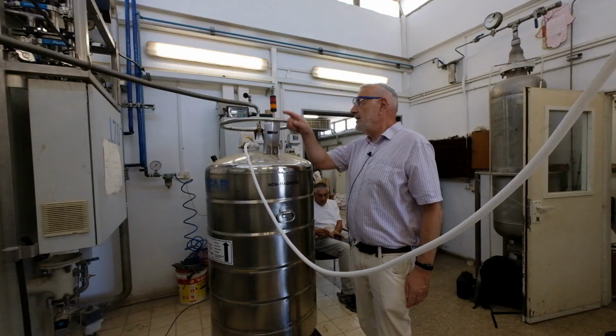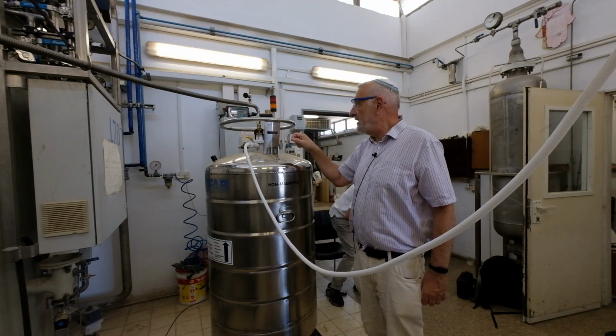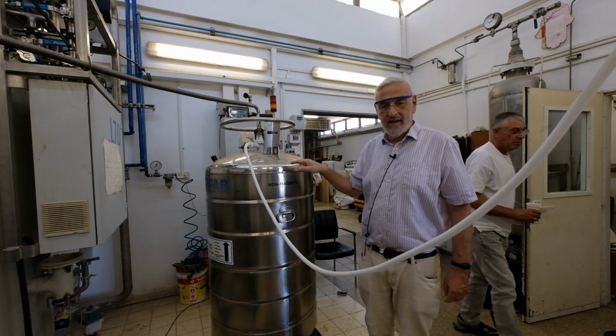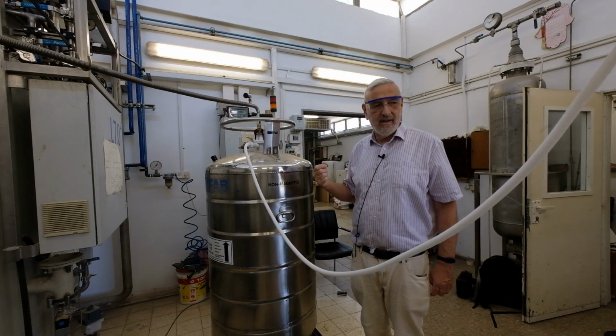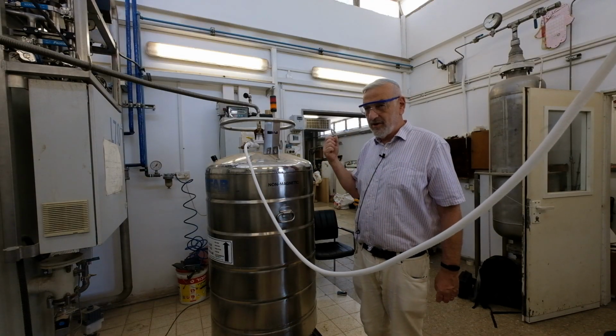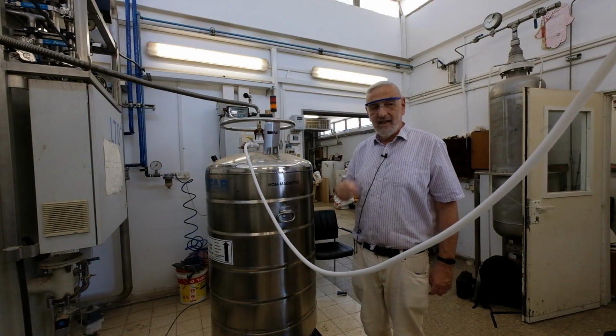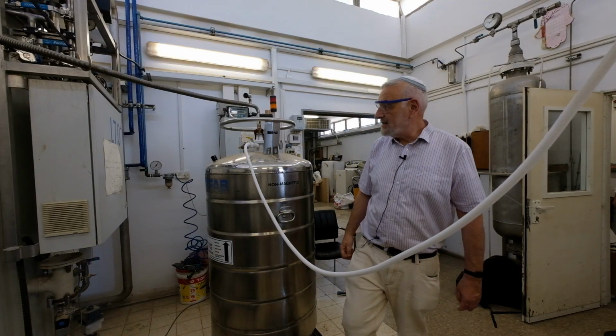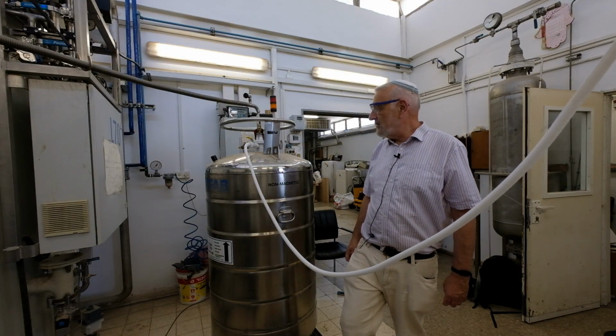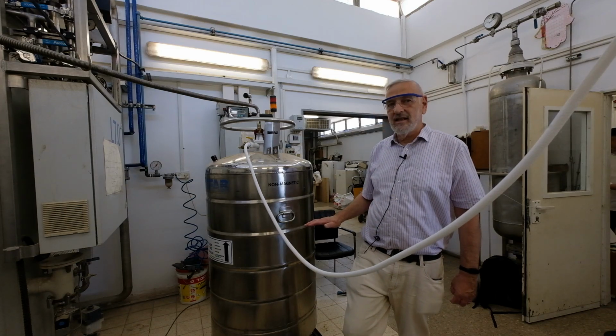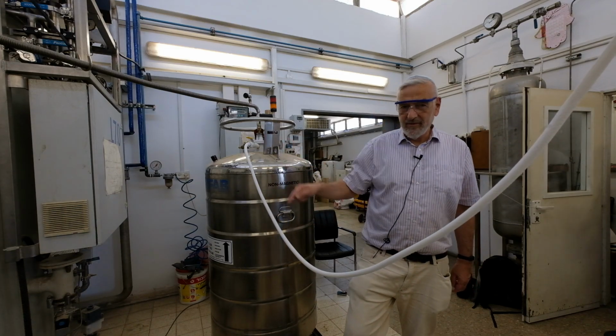In the meantime, the helium is liquefying, the mass is going up, and you can hear in the background the compressor recycling the helium for further use as it evaporates off. There's already liquid helium forming inside and returning it to recycling.